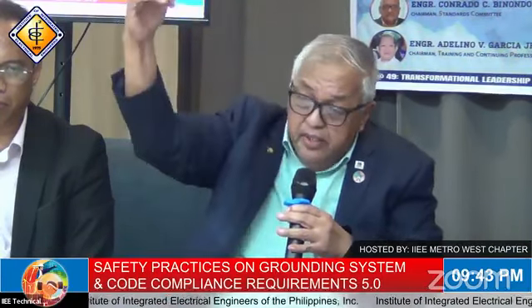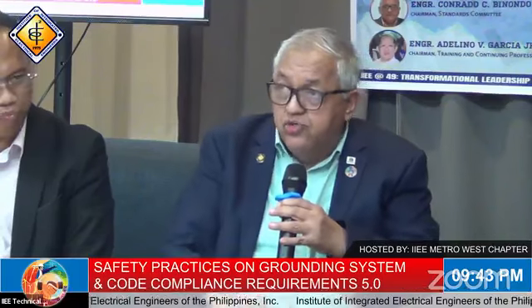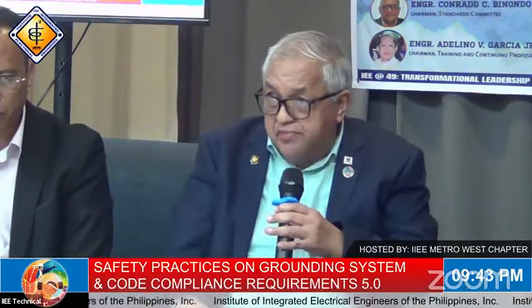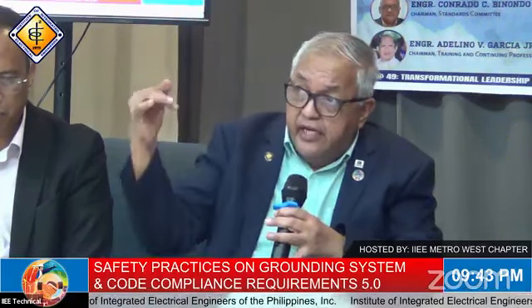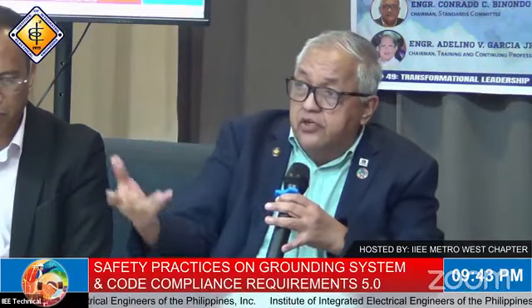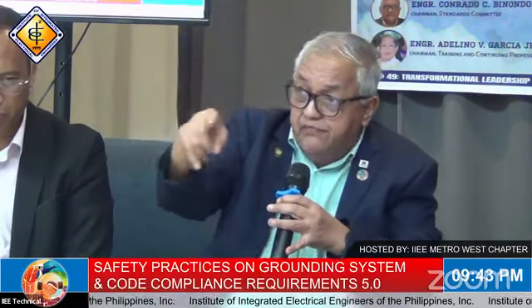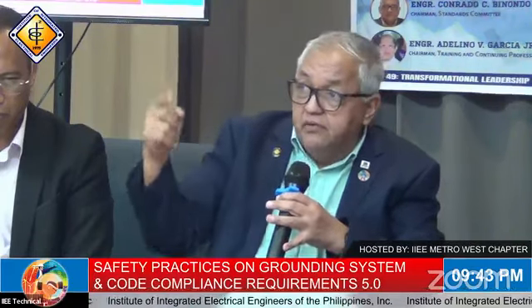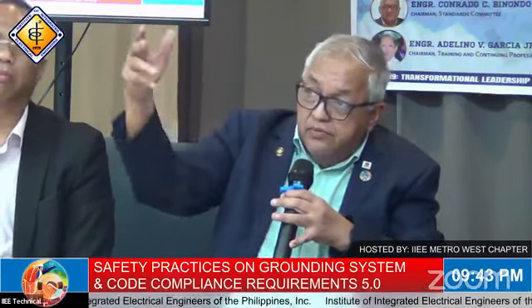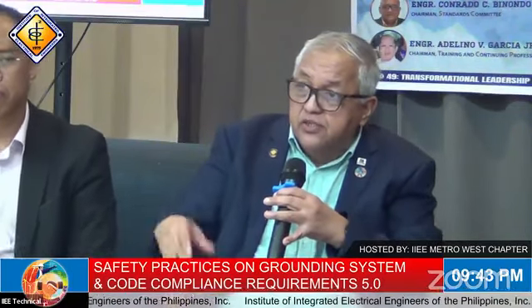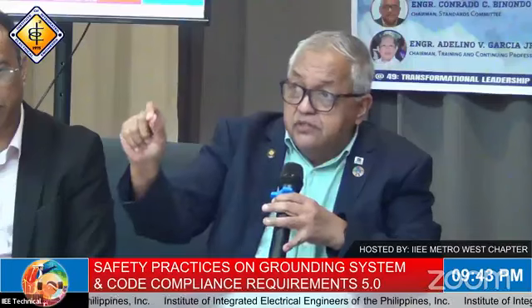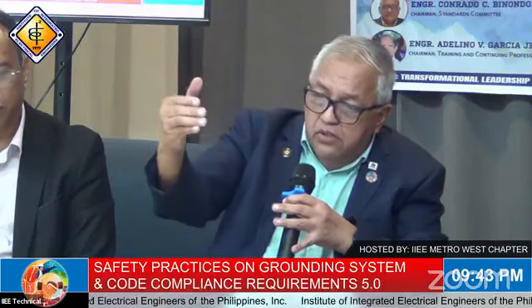So you can use 30 milliamperes below. Pero anong naging issue doon, why they don't use 4 to 6 milliamperes? Because sa Europe, it's 400 volts, so 230 volts ang potential voltage mo line to ground, is higher than sa US na 115. So yung current mo mababa doon sa 115 volts. Sa Europe, it's 230, which ginagamit natin, yung line to ground or line to earth potential. So kapag gumamit sila nun, 4 to 6 pwedeng gawin, because the requirement is not more than 30 milliamperes. So you can go 30, 20, or 10 milliamperes, available lahat yan sa product, but depende sa voltage na ginagamit mo.